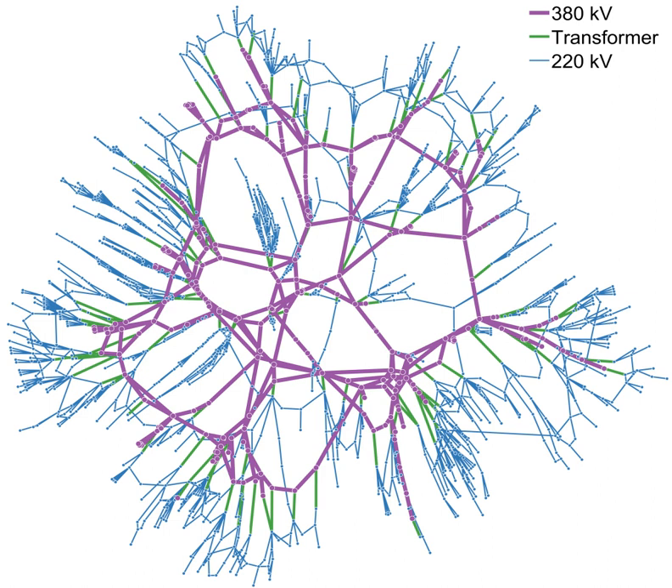The simplest topology for a distribution or transmission grid is a radial structure — a tree shape where power from a large supply radiates out into progressively lower voltage lines until the destination homes and businesses are reached. However, single failures can take out entire branches of the tree. Most transmission grids offer the reliability that more complex mesh networks provide, though the expense of mesh topologies restricts their application to transmission and medium voltage distribution grids. Redundancy allows line failures to occur and power is simply rerouted while workmen repair the damaged and deactivated line. Other topologies used are looped systems found in Europe and tied ring networks.